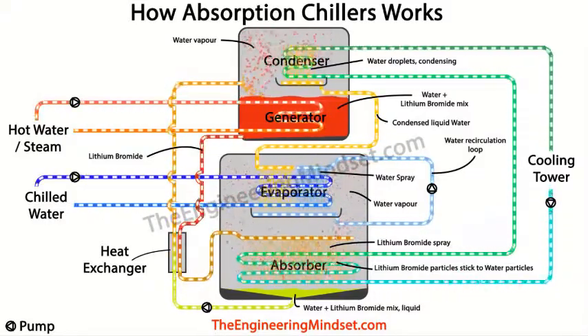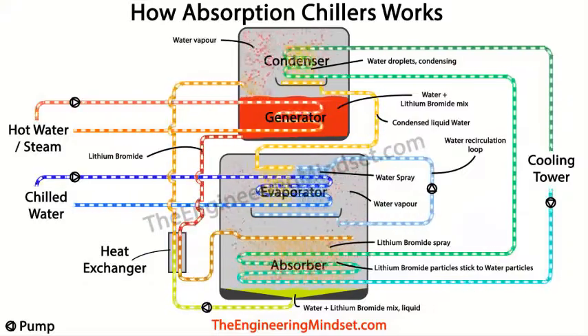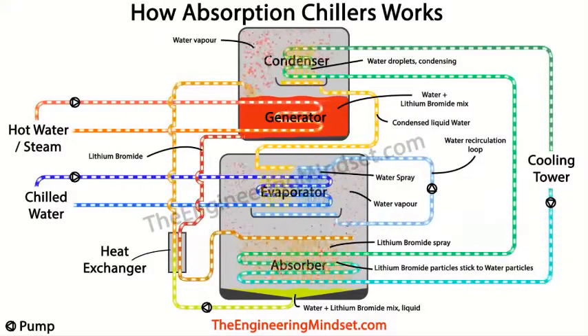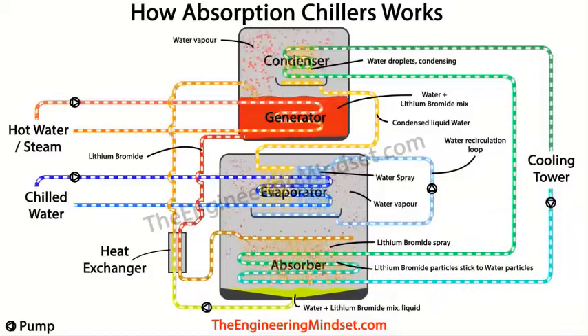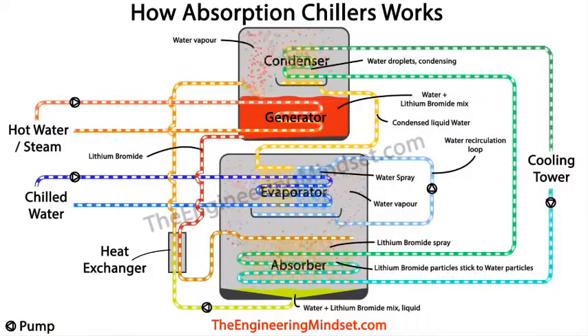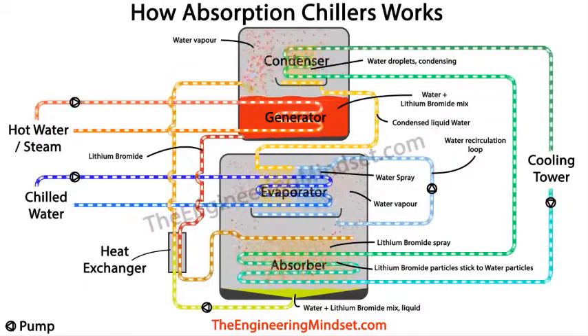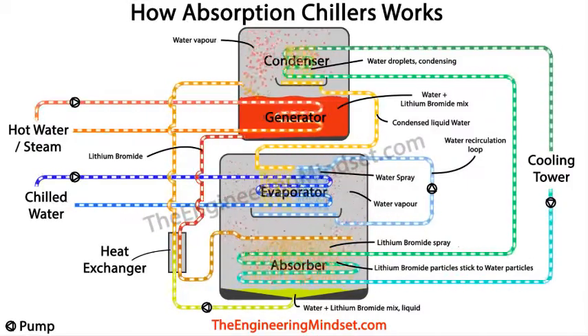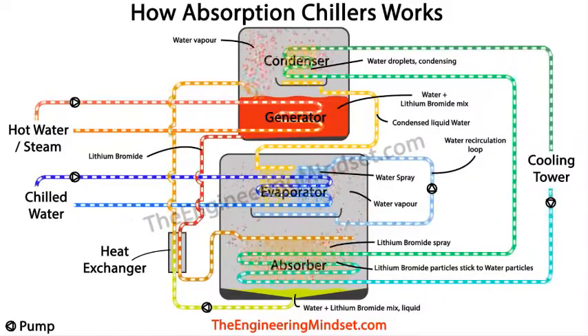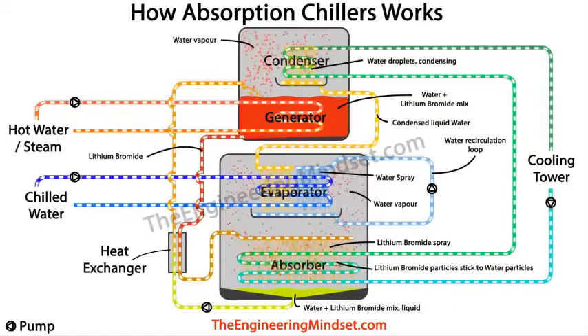Now the cooling tower water will also condense any of the residual water vapor particles or the lithium bromide particles and turn this back into a liquid. And once this has occurred, the mixture of lithium bromide and water is collected at the bottom of the tank in the bottom of the absorber, and it is now ready to be pumped back to the generator again to repeat the entire cycle. So there you have it. That's the basic operation of how an absorption chiller works.